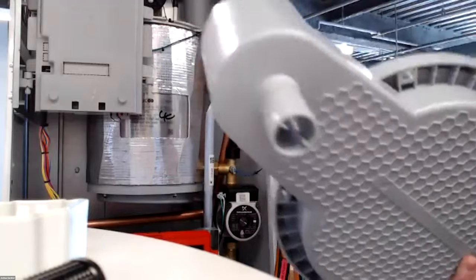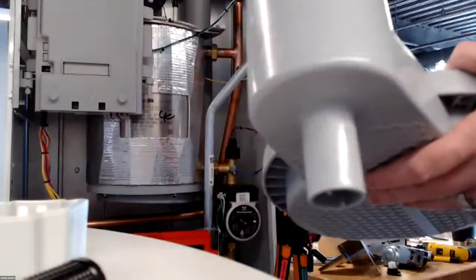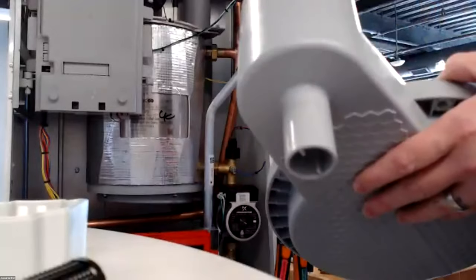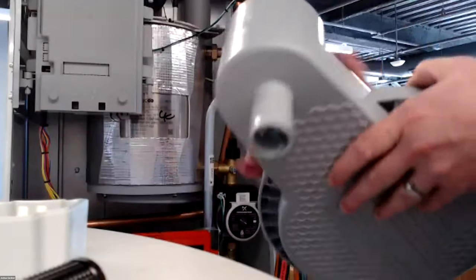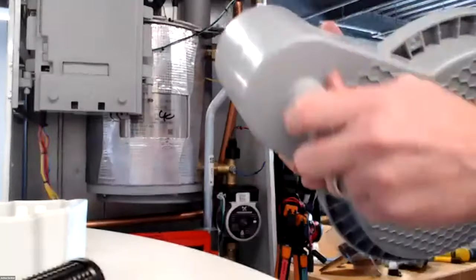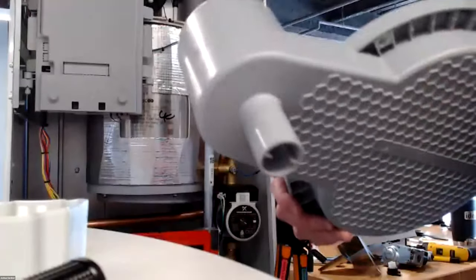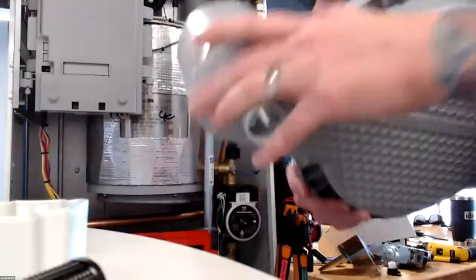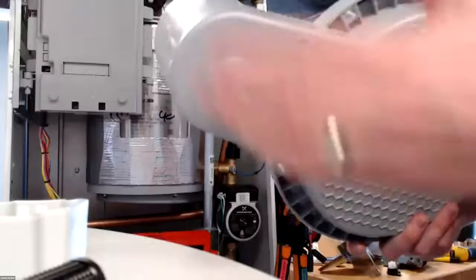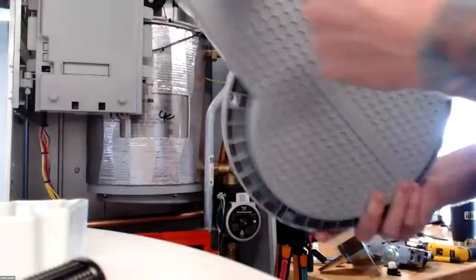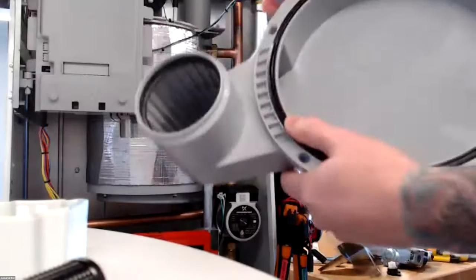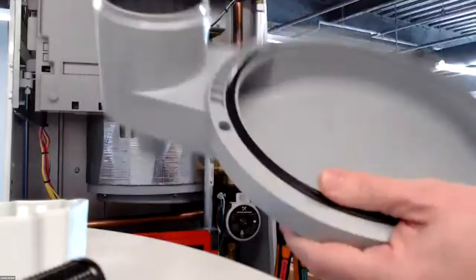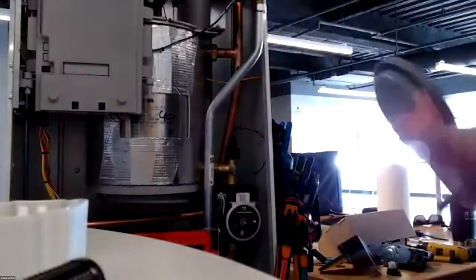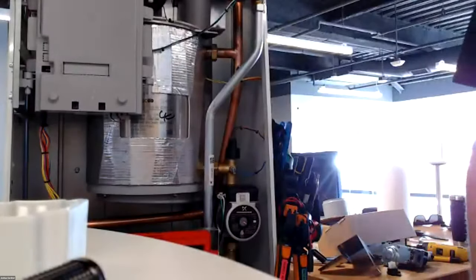On the next series of boilers, we're all going to have the system pumps, so all those condensate traps will be located inside the cabinet. So this being an issue won't be an issue on the next series of boilers, but just be mindful if you're doing the heating only boilers, you just watch out for this nipple so you don't crack it, because then you'll have a leak and you'll call us and you'll need a new pan. And they're fairly easy to swap out, but you don't want to.